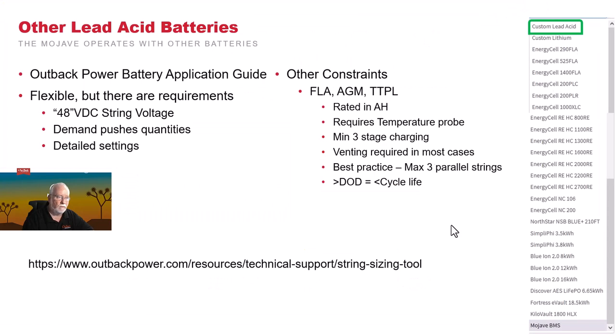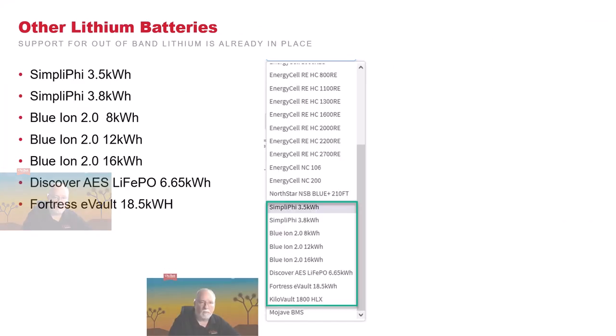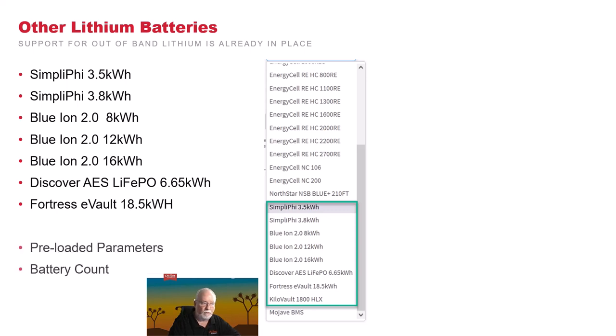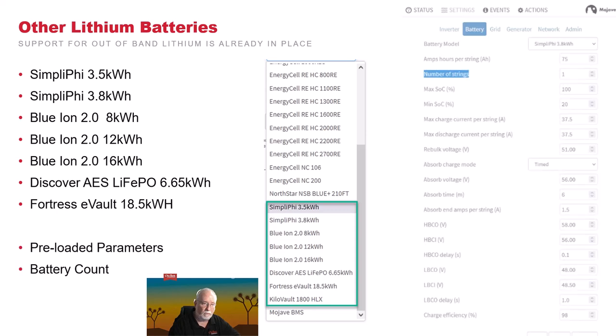So go ahead and close this. So that's other lead acid batteries. Other lithium batteries, we do support the SimpliPhi series, the Blue Ion, the Discover. We go through. The nice part is there are additional values that you can get. They're preloaded. You just simply put in the battery count. So in here, this is an example of the SimpliPhi 3.8. All we do is increment the number of strings, which in this case would be batteries, because it's a 48-volt string. Put them in, and then you hit submit, and you're ready to go.